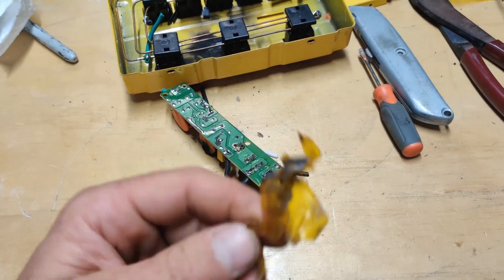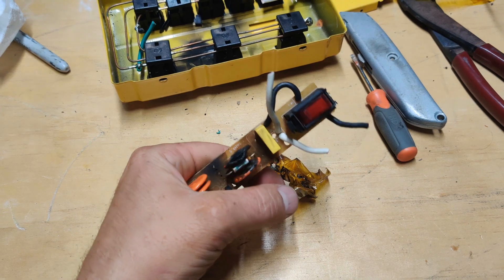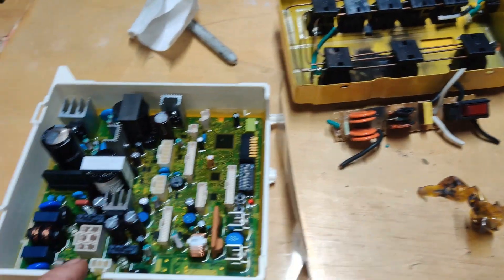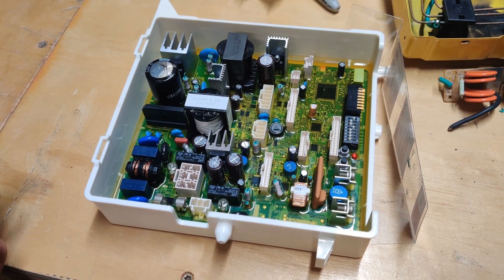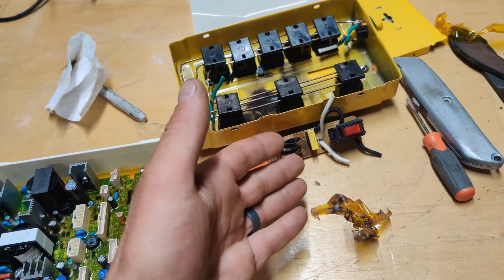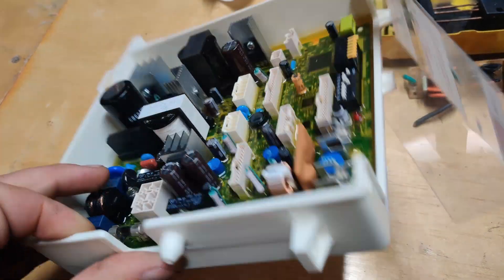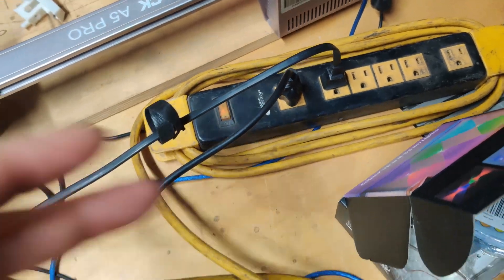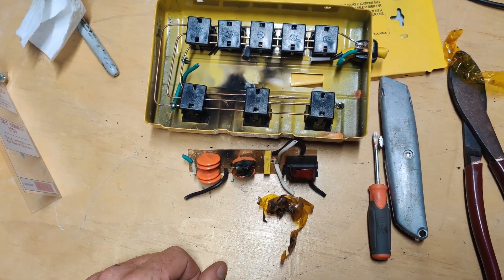All because we tried to rely on tape as an isolator — and when the varistor blew, it melted. So anyway, am I a little freaking pissed? Yeah. Is it likely this caused the water heater damage? Well it sure as hell didn't protect it. Maybe it was dumping some current — I don't know. This sucks, it hurts. What sucks even more is how dangerous this thing was. It's definitely going to make me think twice and consider opening this other one, which is also metal. Can't rely on tape. That's all I got.